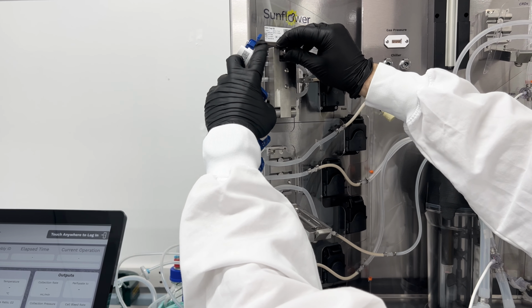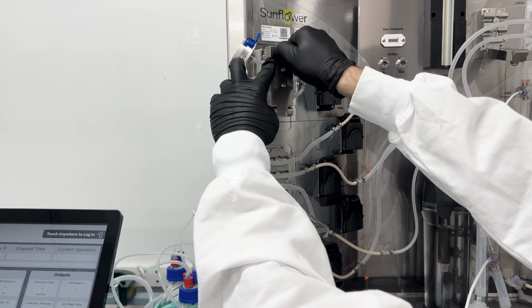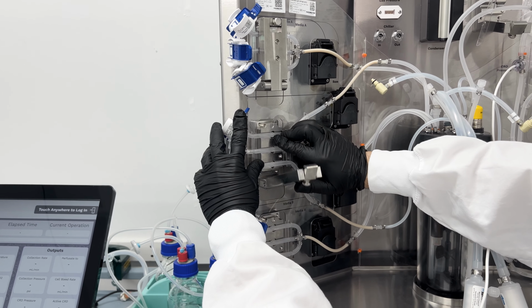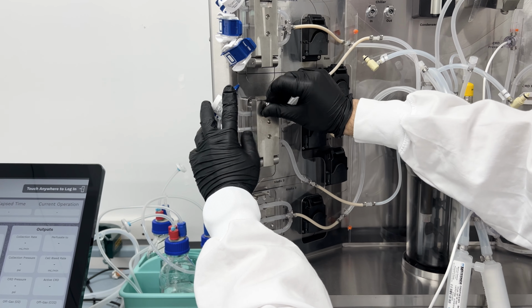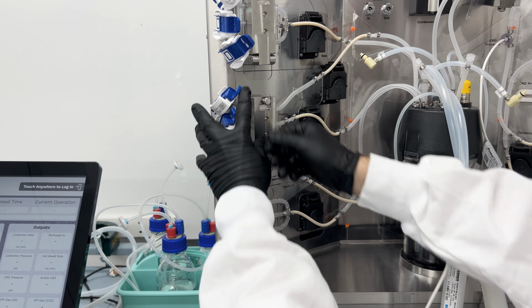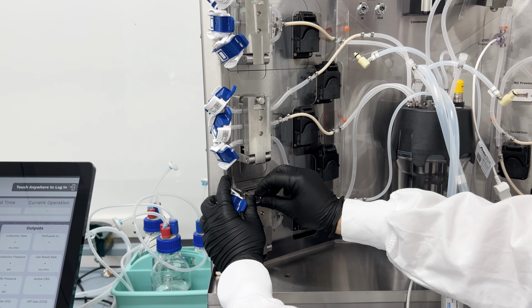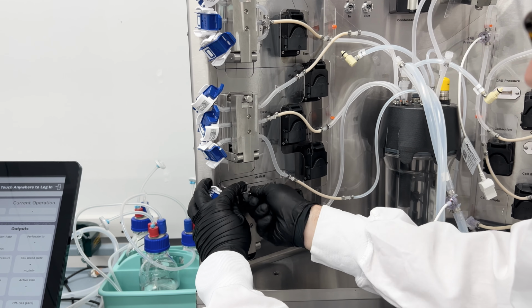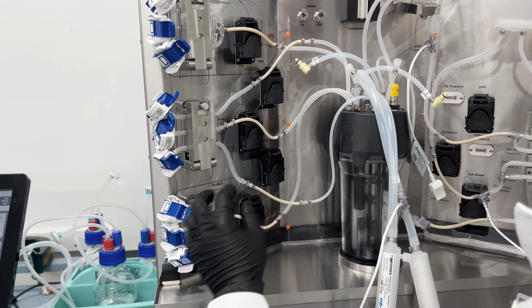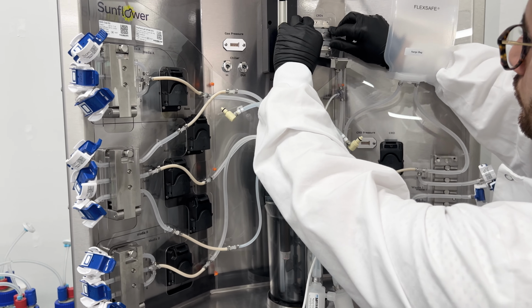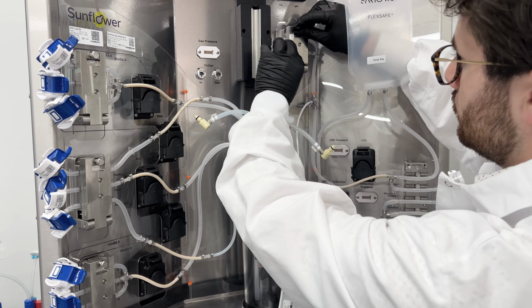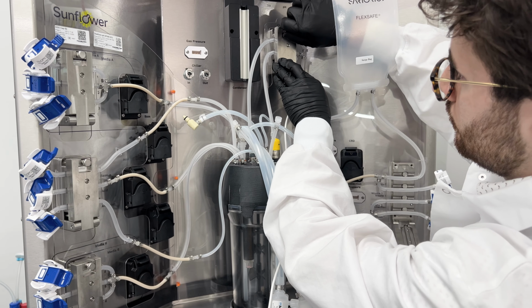Hold the loom so that the tubing is seated in each channel. Close the door and press the valve gate latch forward and down to secure it. You will hear and feel a firm click when the latch has caught. Then, tighten the thumb screw until it is finger tight. We'll repeat the same process for each of the valve gates. Each valve within the valve gate controls one fluid flow path. The opening and closing is automated to create the flow path defined by the recipe.